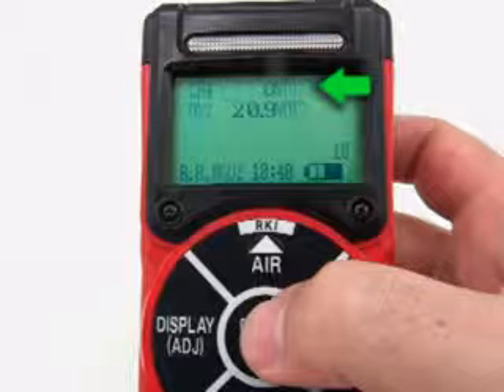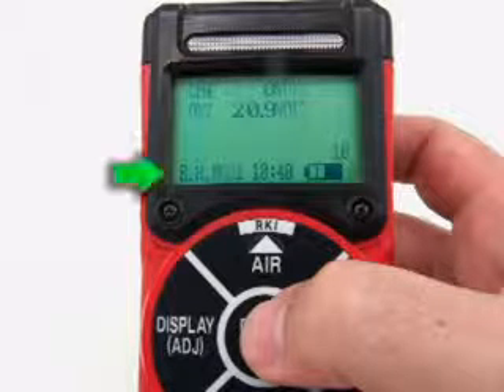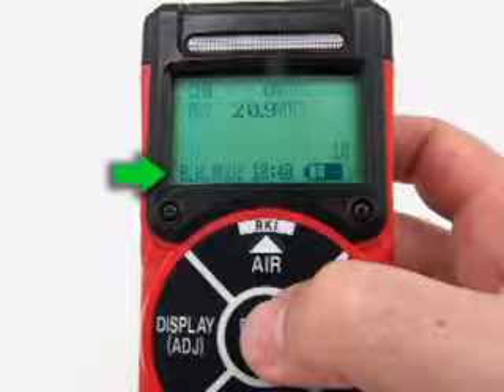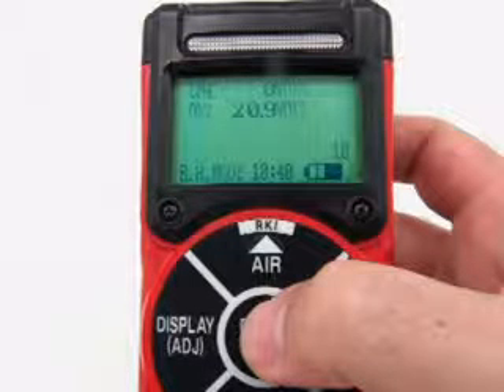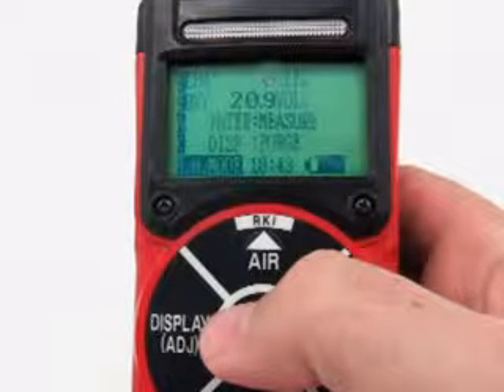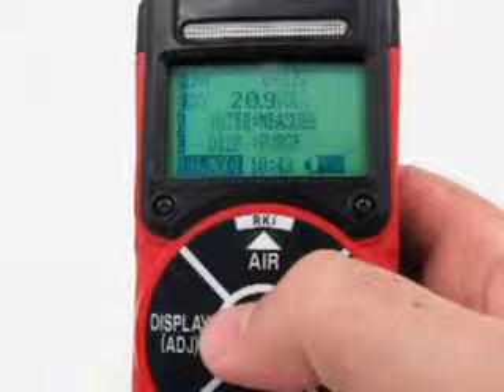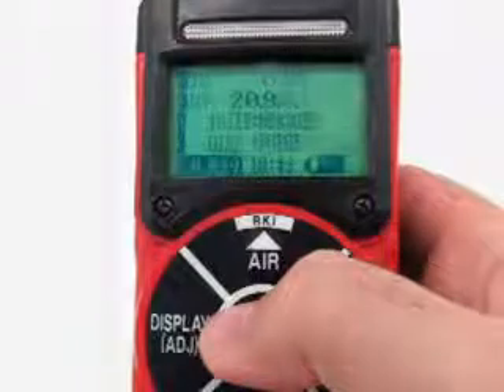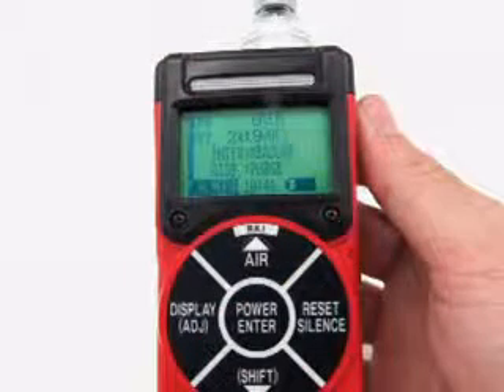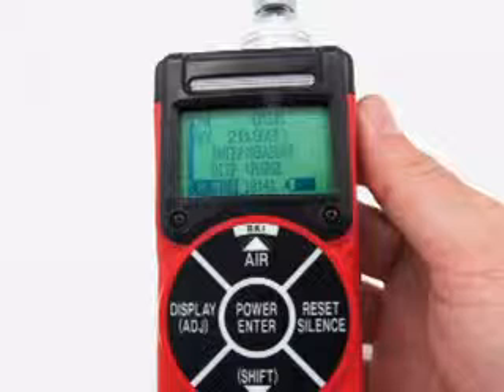The methane channel will be displayed in percent volume and the message BH mode will be flashing. After 15 seconds of sampling, if the methane reading is less than 5% volume, the methane channel will automatically begin displaying in percent LEL. At the end of the sample period, the pump will shut off and the audible alarm will sound. The peak methane reading and the minimum oxygen reading for the sample period will then be displayed.